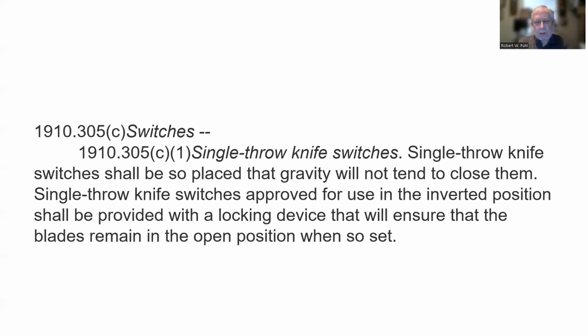Single throw knife switches. Single throw knife switches shall be so placed that gravity will not tend to close them. And a knife switch is a switch like this and like that. That's pretty much the knife switch. A single throw knife switch approved for use in the inverted position, upside down, shall be provided with a locking device that will ensure the blade remains in the open position when so set.